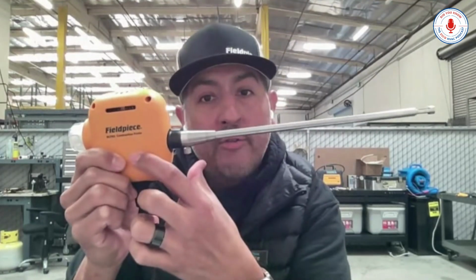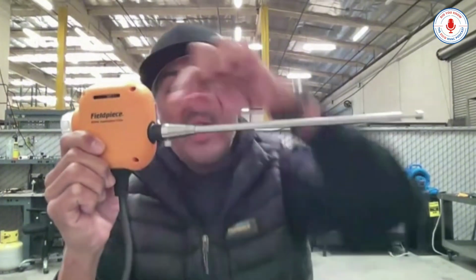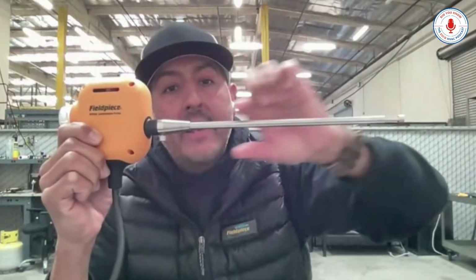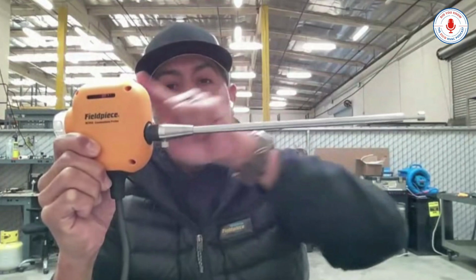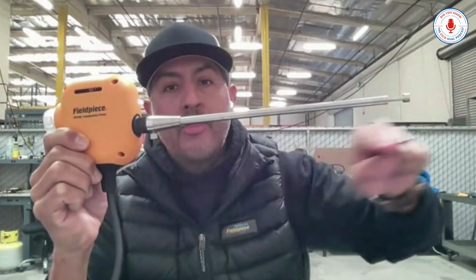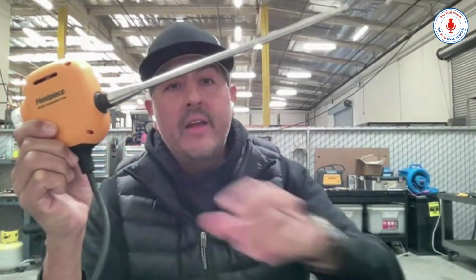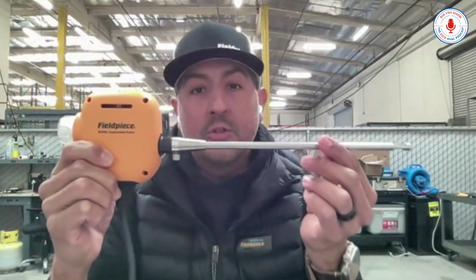And instead of storing it for you, there's a secondary pump that is just pumping it back out into the flue from where it came. So it's just cycling through here, and there's no need to have a water trap anywhere else downstream, and there's nothing to maintain. So the hydrocycle pump just takes away one thing that we have to consider to maintain the combustion analyzer. Absolutely. How far into our flue gas stream are we going to be inserting our test probe?